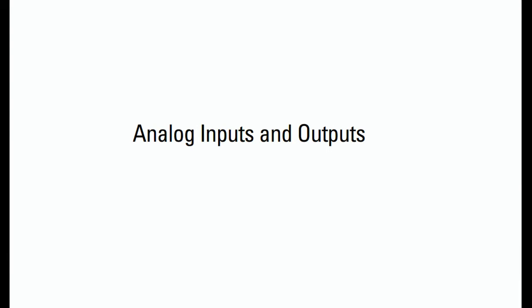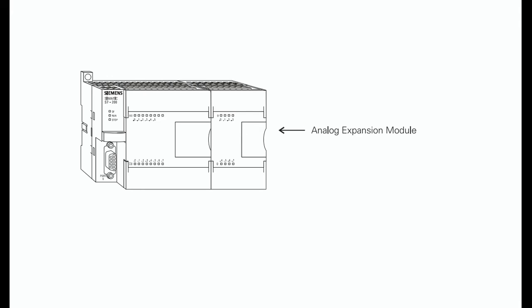Analog inputs and outputs: PLCs must also work with continuous or analog signals. Typical analog signals are 0 to 10 V DC or 4 to 20 mA. Analog signals are used to represent changing values such as speed, temperature, weight, and level.